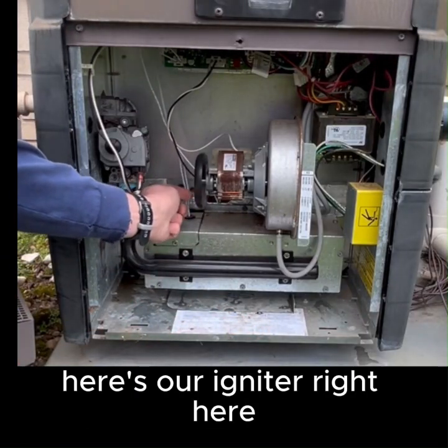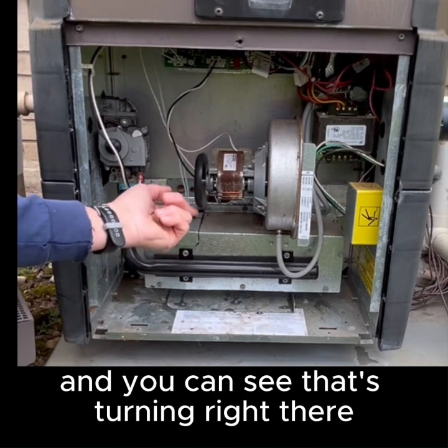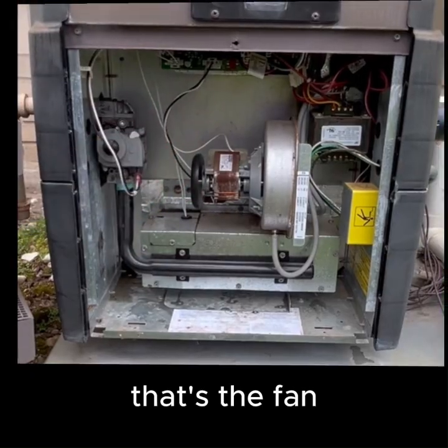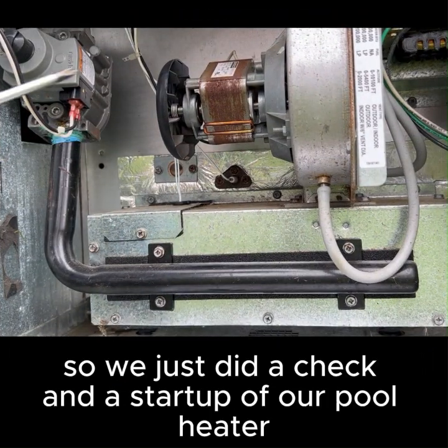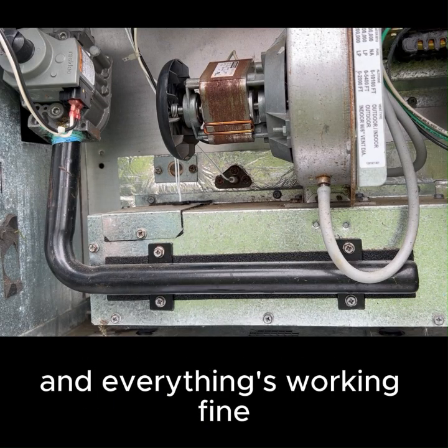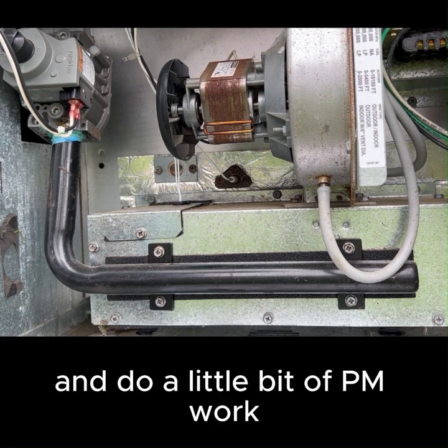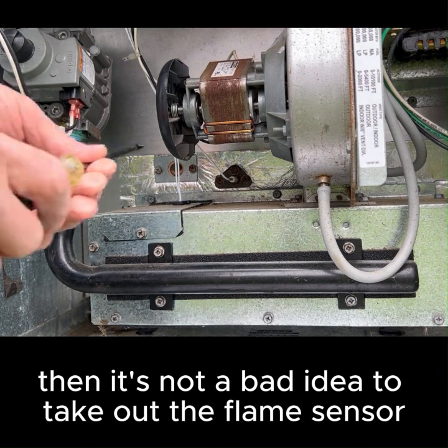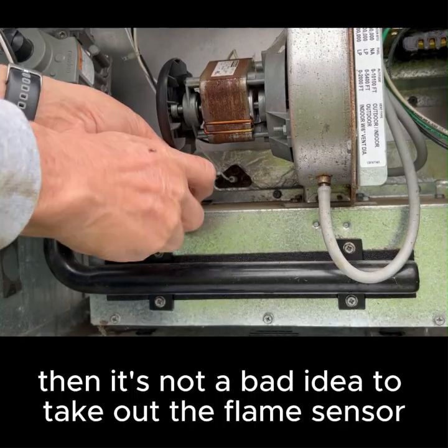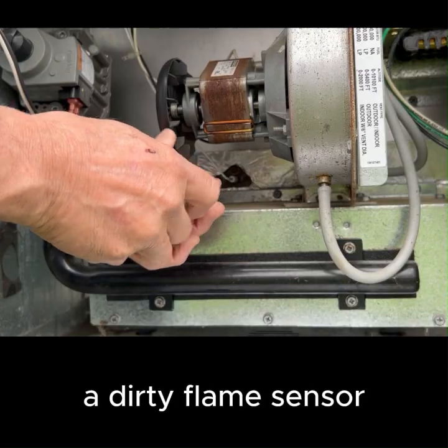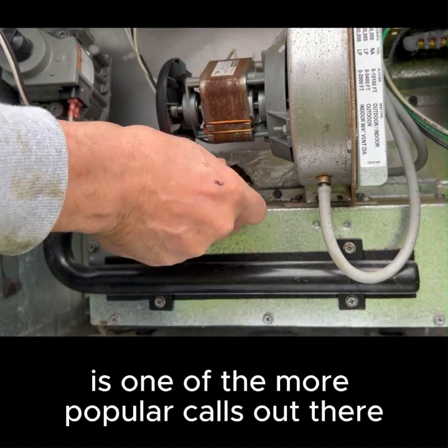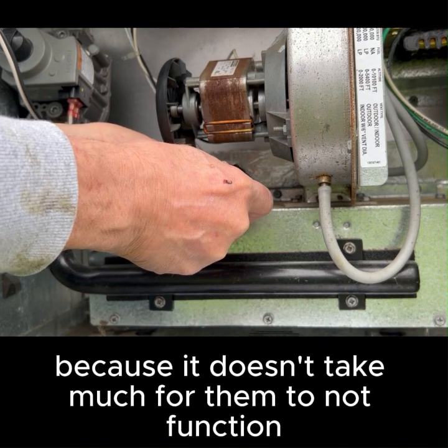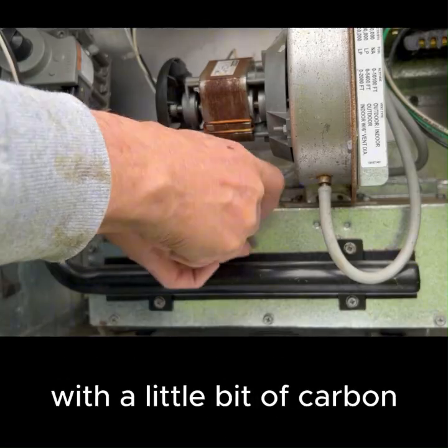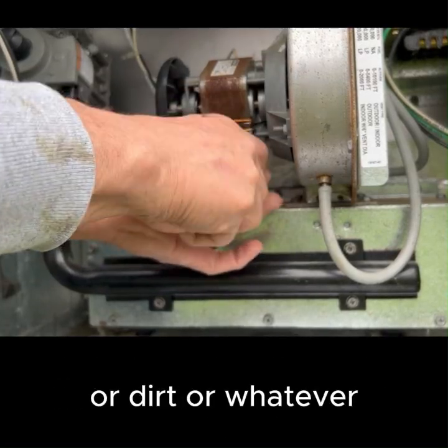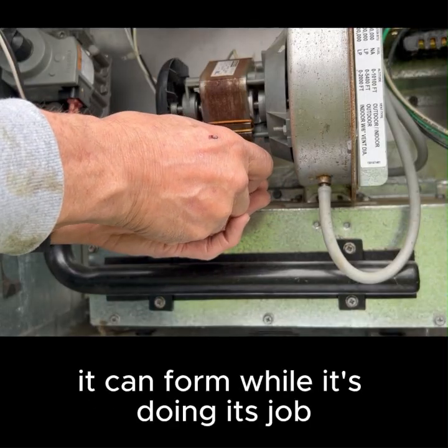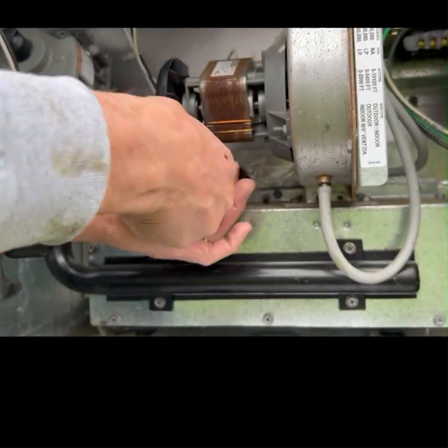Here's our igniter right here, and there's our flame sensor wires right there. And you can see that's turning right there. That's the fan. So we just did a check and a startup of our pool heater, and everything's working fine. But if you wanted to go the extra step and do a little bit of PM work, then it's not a bad idea to take out the flame sensor and clean it. A dirty flame sensor is one of the more popular calls out there because it doesn't take much for them to not function, with a little bit of carbon or dirt or whatever it can form while it's doing its job. There's 3 screws, fairly easy to take out.